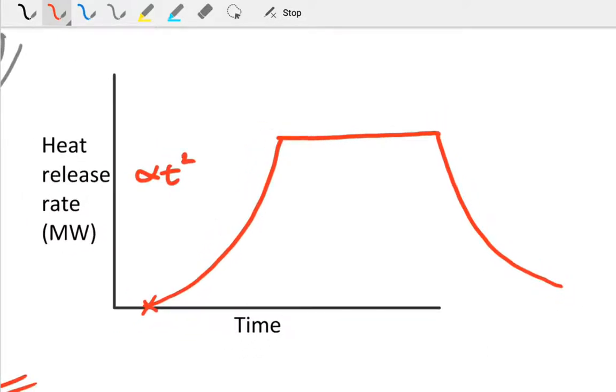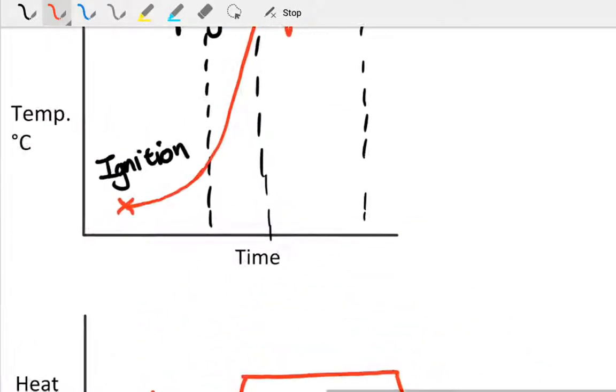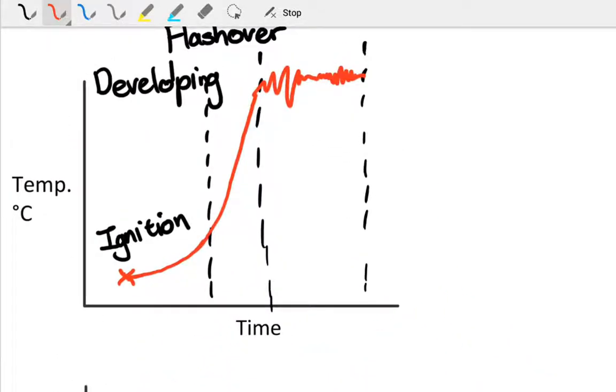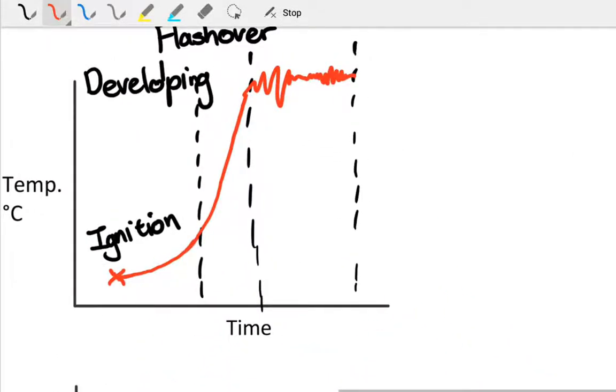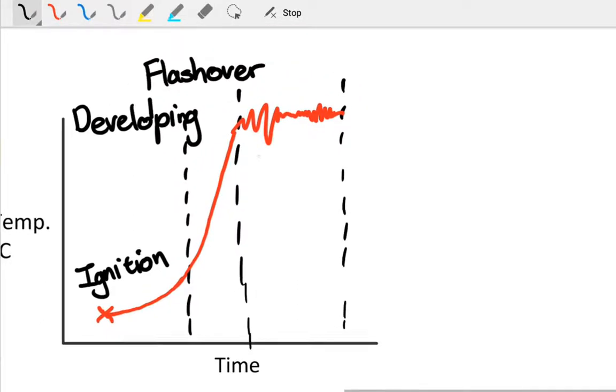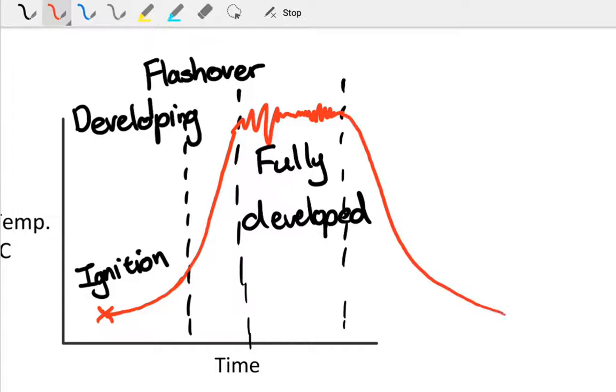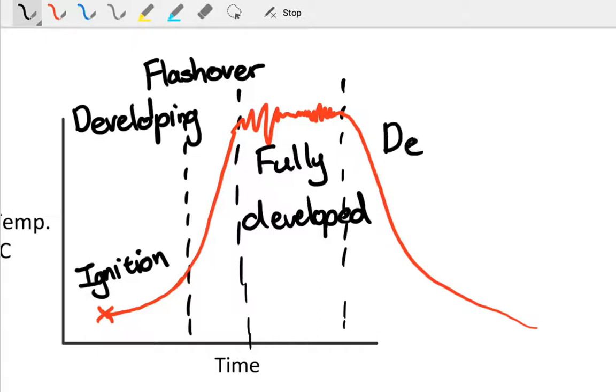That's what your heat release rate might look like. Associated with that, once the fully developed stage is finished—coming back to our time temperature curve, there's our fully developed stage—once that has passed and the material has been consumed which is burning, we'll enter the decay phase where it'll swap to being fuel controlled again. You don't have enough fuel to burn. This is our decay phase here at the end, and it'll gradually then go from fully developed and sort of die out as the last of the fuel is consumed.